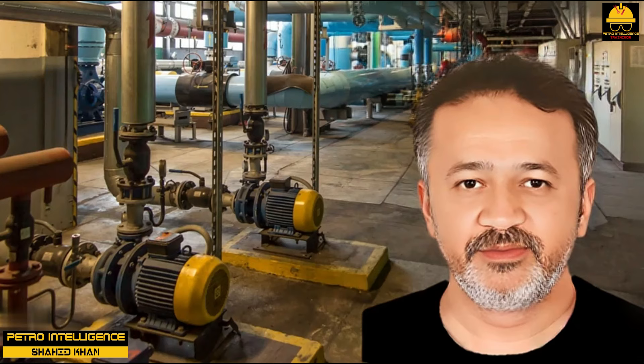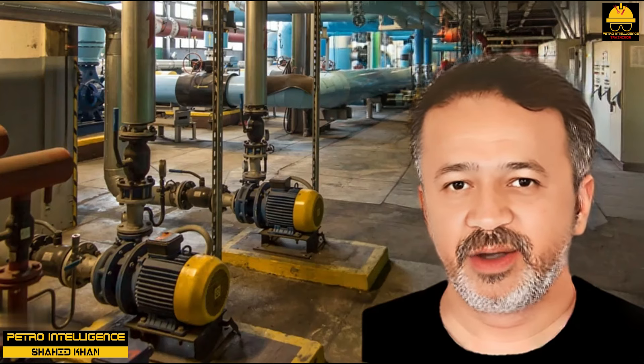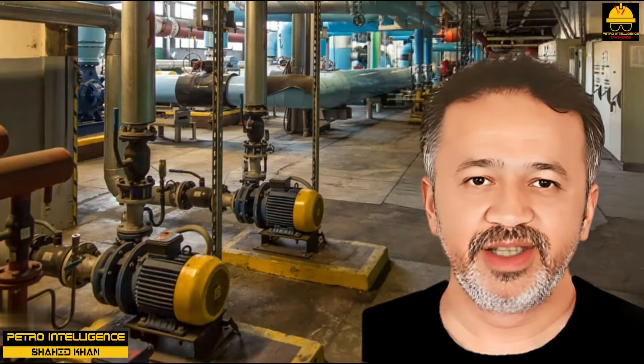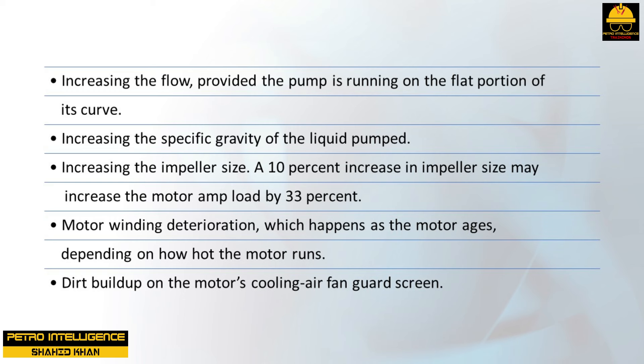Factors that increase the amp load on a pump's motor driver are: increasing the flow, provided the pump is running on the flat portion of its curve; increasing the specific gravity of the liquid pumped; increasing the impeller size — a 10% increase in impeller size may increase the motor amp load by 33%; and motor winding deterioration, which happens as the motor ages depending on how hot the motor runs.